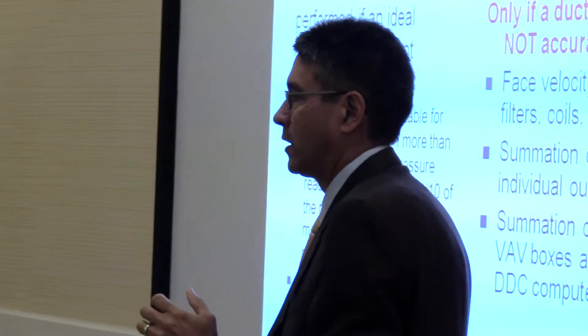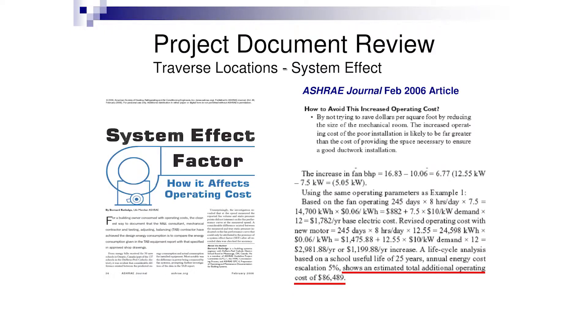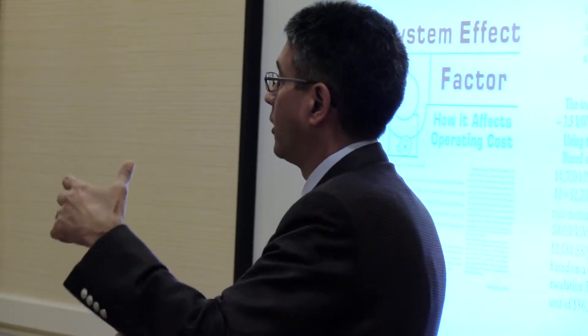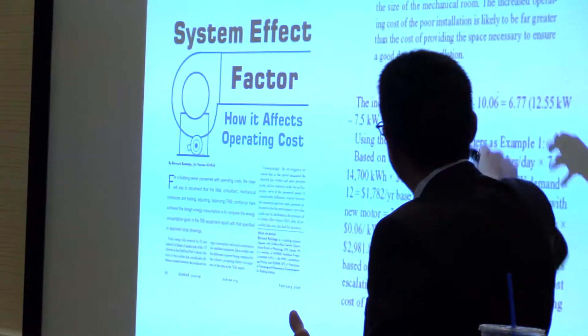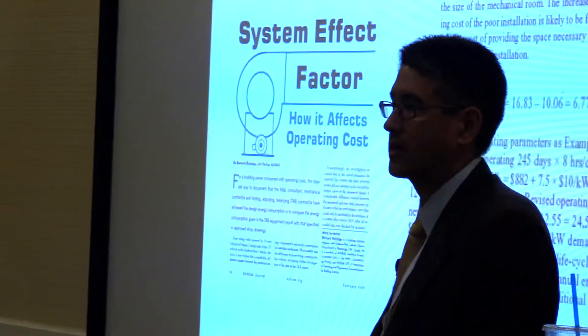We love a traverse — everything we try to do airflow measurement-wise is always backed up by a traverse. ASHRAE back in 2006 published an article on system effect factor and how it affects operating cost. A school district in Canada studied all their schools, determining how much system effect was affecting all their fans and air handlers. In one example, they were reducing 6.77 horsepower on one air handler — saving roughly $1,200 a year with a straight duct run. Taken over 25 years life cycle cost, that was $86,000 for just one unit.